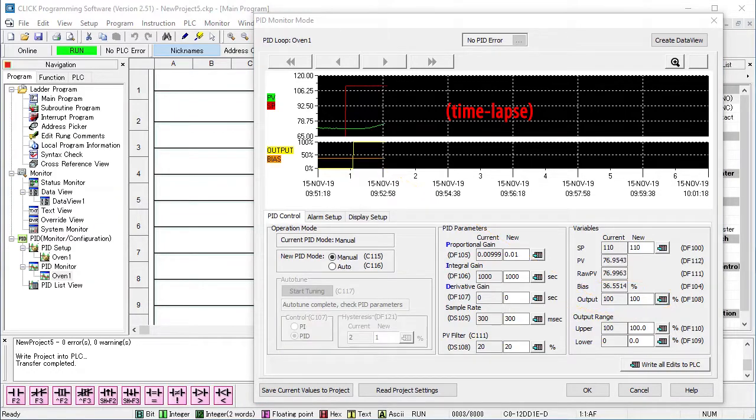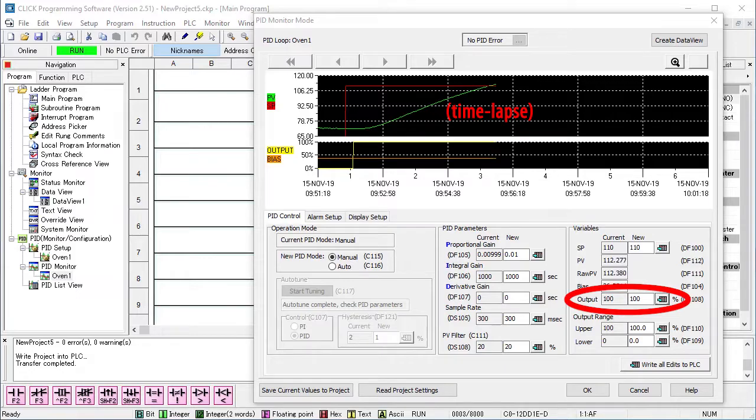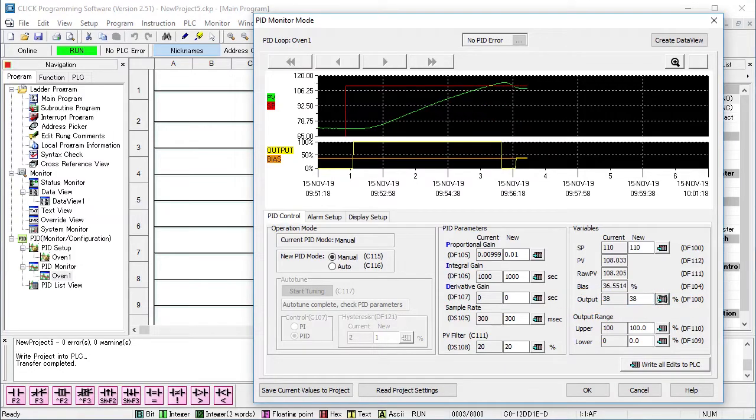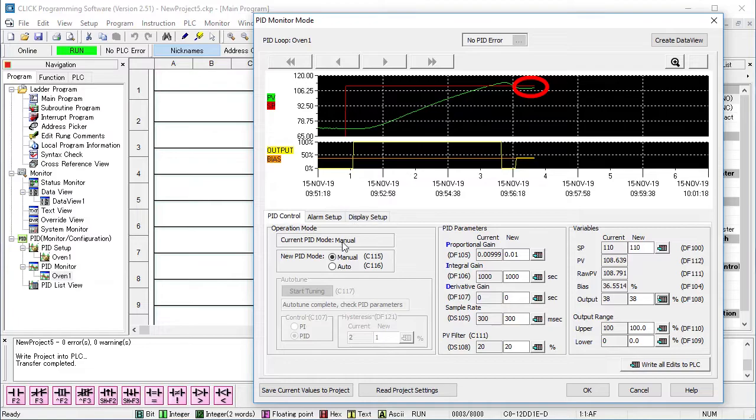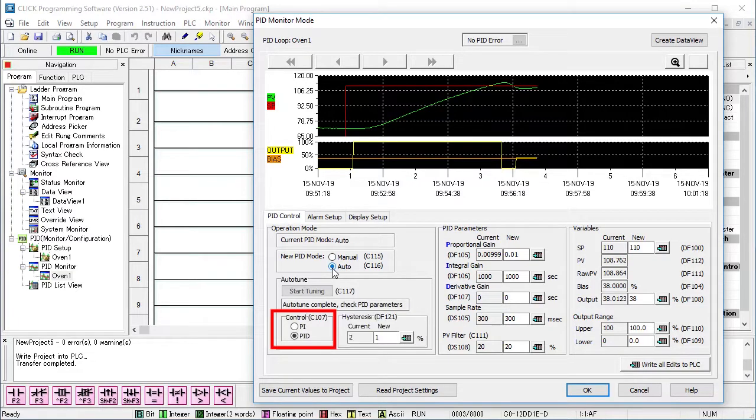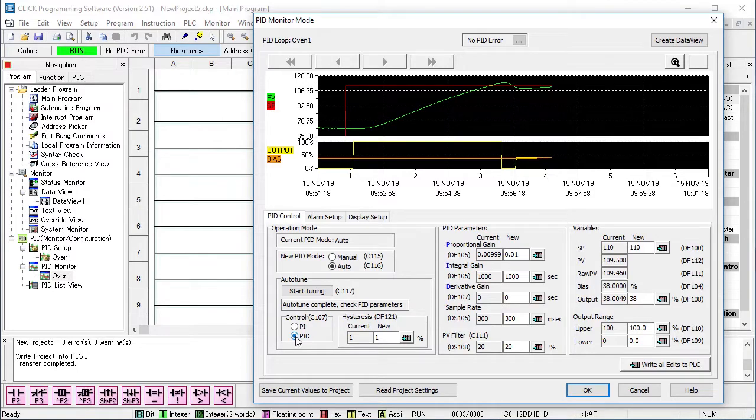It will take a while to get the oven up to temperature, so I'll fast forward the video and tweak the display axis as we go. Now that our process is close to our set point and stable, flip over to auto mode, select the algorithm type and enter the hysteresis you need. Hit start.